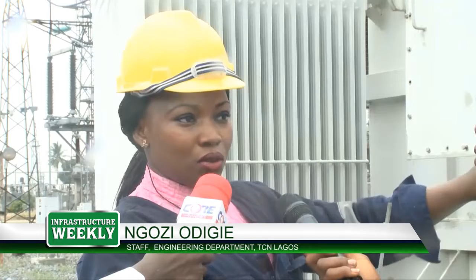So the function of the silica gel is to allow the air to pass through it before getting into the transformer. Why is air moving? The ambient temperature within the transformer changes as it's working and with the environment. When there is a higher temperature, the oil inside increases in volume, sort of. So we leave a little space in the conservator tank, just a spare tank for extra oil. So the oil will rise there instead of spilling out or there being excess pressure within the transformer tank.